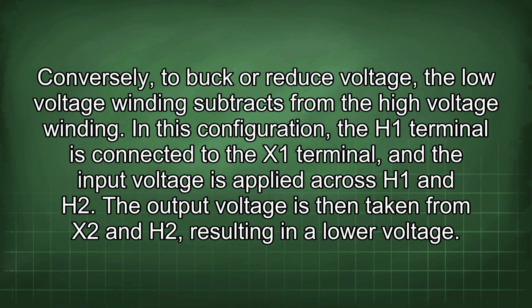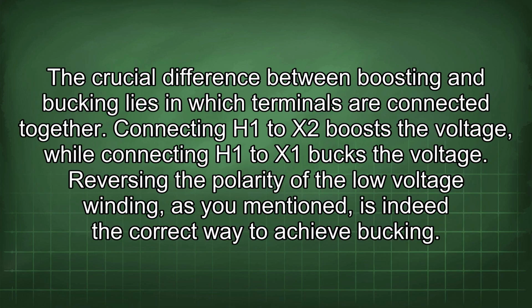Conversely, to buck or reduce voltage, the low voltage winding subtracts from the high voltage winding. In this configuration, the H1 terminal is connected to the X1 terminal and the input voltage is applied across H1 and H2. The output voltage is then taken from X2 and H2, resulting in a low voltage. The crucial difference between boosting and bucking lies in which terminals are connected together. Connecting H1 to X2 boosts the voltage, while connecting H1 to X1 bucks the voltage.